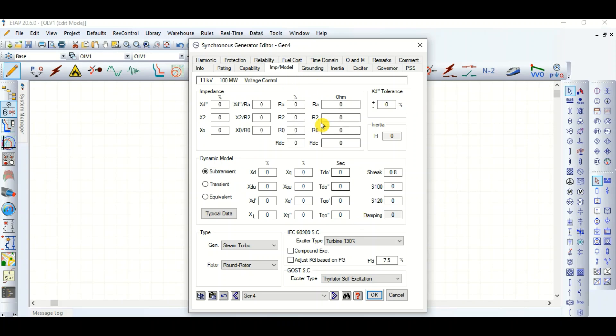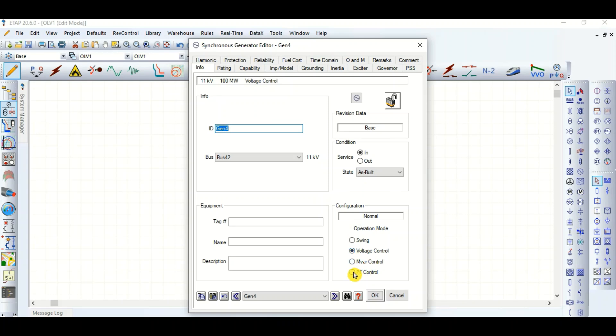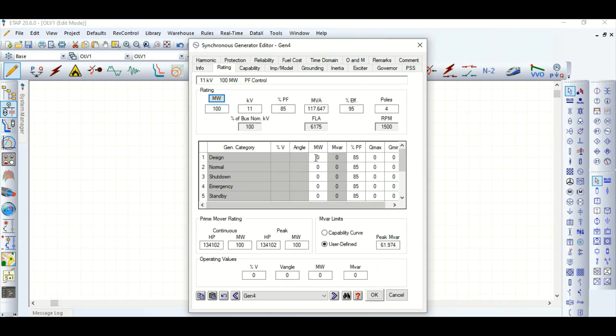The transient reactance is set to a typical value and it is in voltage control mode. Maximum real power is 100 megawatt, and corresponding to 85% power factor the maximum reactive power the generator can supply is 61.974 MVAR. On the negative side, at 95% leading power factor, it can absorb minus 32.86 MVAR.